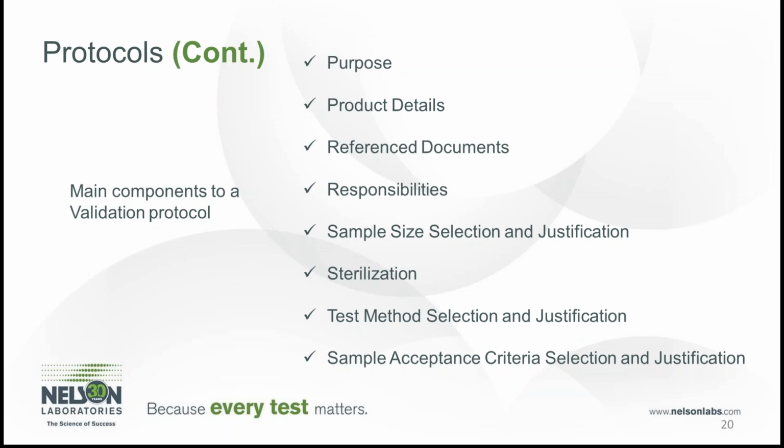These validation protocols can reference other protocols like those individual test method protocols. By referencing those smaller test method protocols, updates can be made to those without jeopardizing your validation or master protocol.